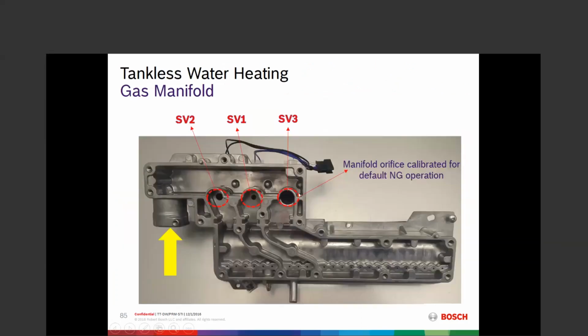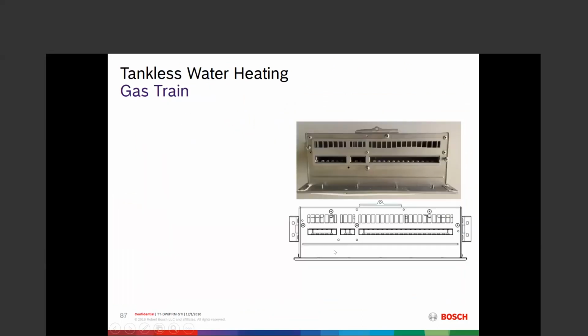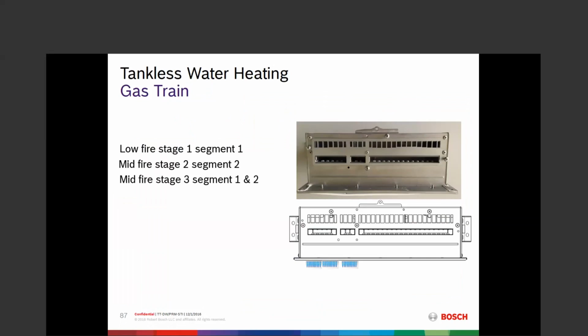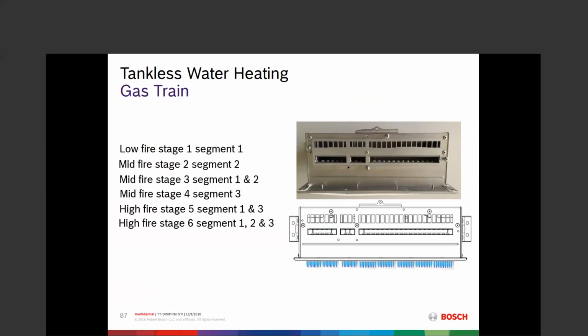Let's see the injectors, what it looks like in the actual flow of the fuel as it's coming in. The staging looks like this. Probably pretty obvious on the staging that stage 1 would in fact be segment 1. If you thought that, you'd be right. And if you thought that stage 2 would be segment 2, you'd also be right. But if you thought that stage 3 was segment 3, you'd be wrong. It's segment 1 and segment 2 together. Stage 4 is segment 3. Stage 5 is segments 1 and 3. And stage 6 is everything's lit all the way across. And that's how it's going to modulate. So it modulates independently within the stage and then across all the stages.